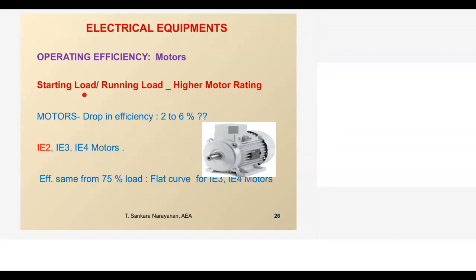There is a starting load and a running load, due to which a higher motor rating is selected. Normally the torque requirement is calculated, then they will add another 20% for the motor. For certain equipment, the starting load may be higher, and during running it may have a lower load. But invariably, the motors have a higher rating, so these motors will be operating at a lower load. So the drop in efficiency, the range is given. We can take for a particular motor how the efficiency drops.